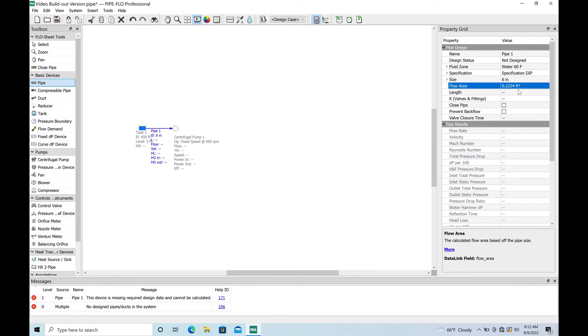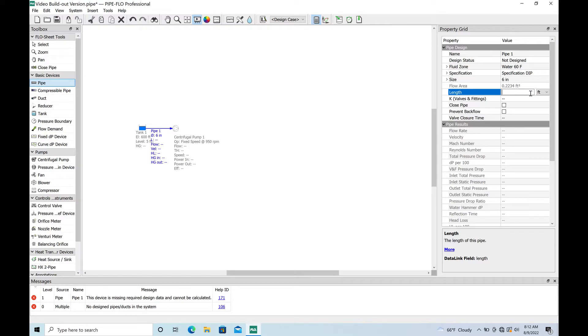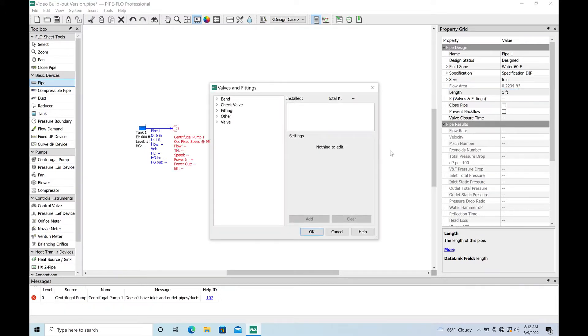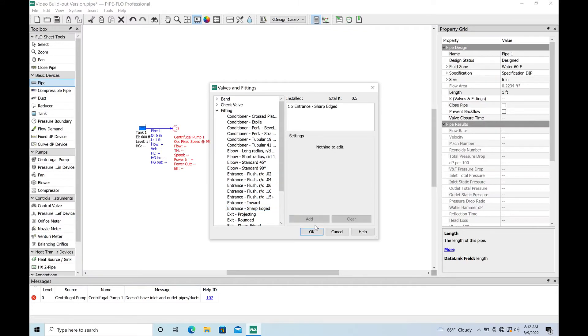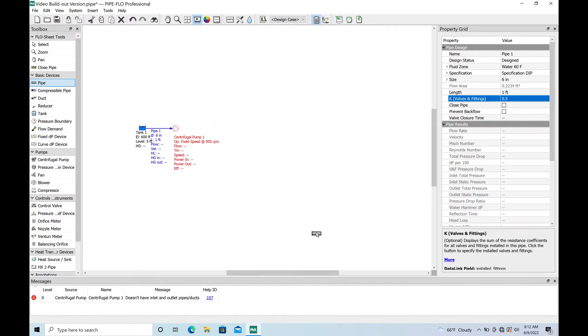There's our pipe, it's coming in. This is pretty cool, you're getting your areas and it's going to do your c-factor for you. Let's go ahead and put in an entrance loss, it's not a big deal. Sharp edge, there's our point five, we're adding it there. Boom, done. Now we've got our pump.